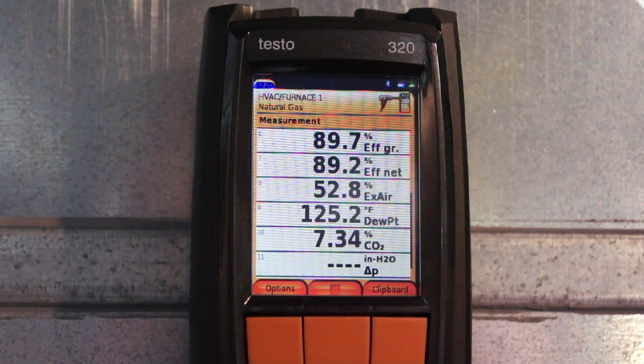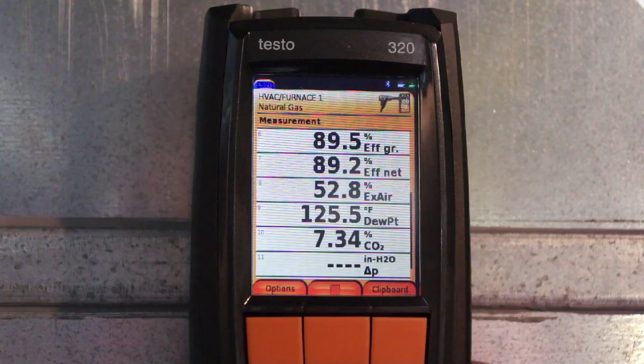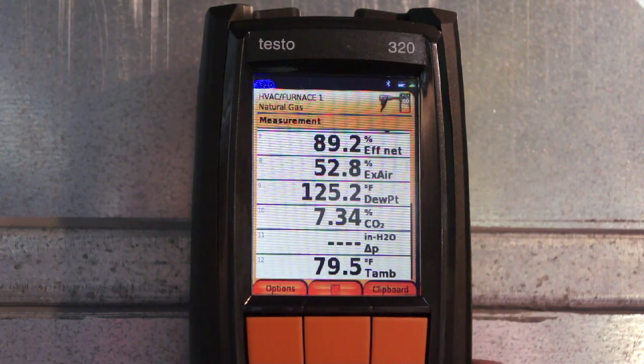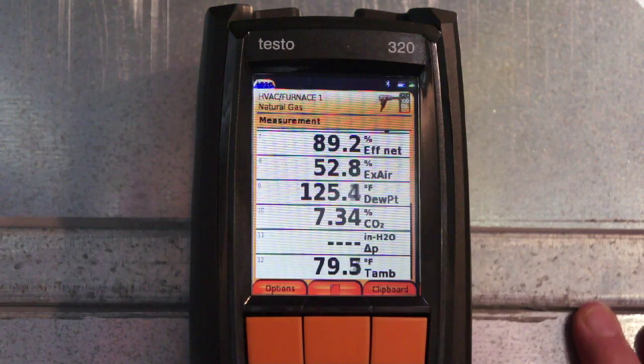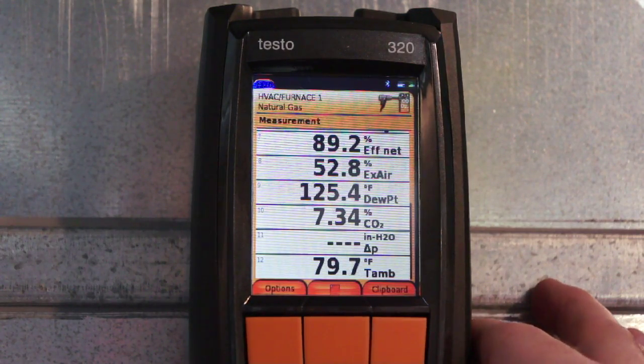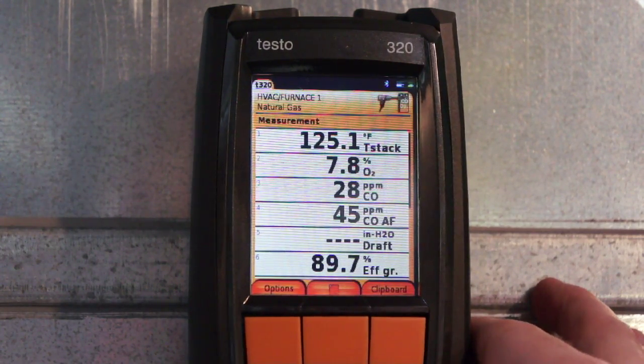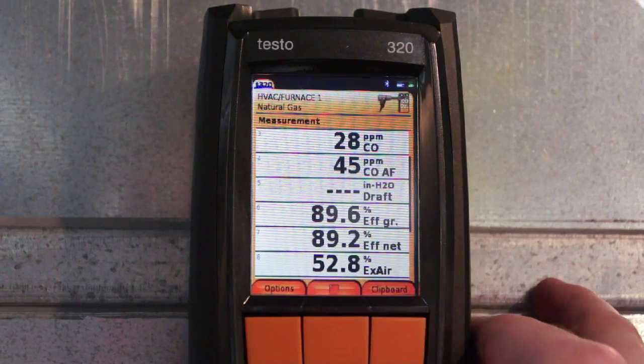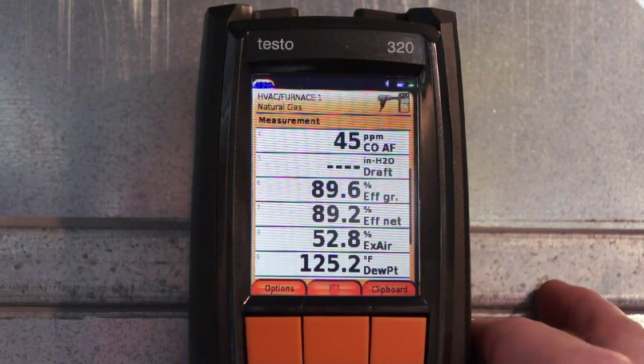Scroll down again, I have my inches H2O. If I measure differential pressure, like a gas pressure, I want to record that on here. I could have that on the display. It's dashed because I haven't measured it. Scroll down again, I have my ambient temperature. And this is tied to the appliance, so I think we're reading the temperature of the instrument. Scroll back down again, I have gross efficiency, net, and we can go back up to the top again.